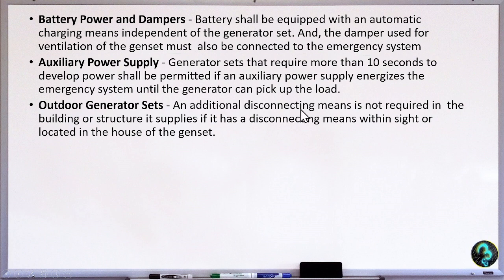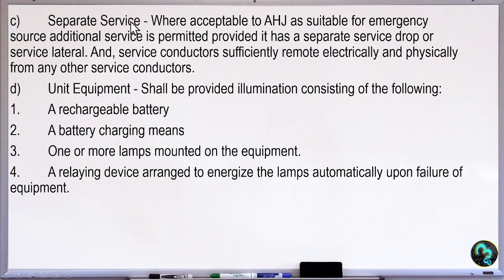Outdoor generator sets and additional disconnecting means is not required in the building or structure if it has a disconnecting means within sight or located in the house of the genset. Okay, so separate service where acceptable to the authority having jurisdiction as suitable for emergency source, additional service is permitted provided it has a separate service drop or service lateral and service conductor sufficiently remote electrically and physically from any other service conductor. So we could allow separate service if that is approved by the building official, or any authority having jurisdiction, if that service is for emergency source. It should be approved.